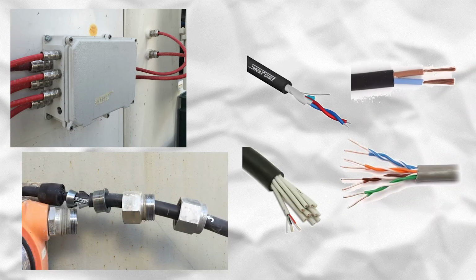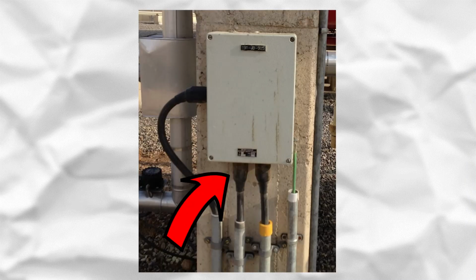In the construction stage, a contractor would follow the drawing designed in the engineering stage and install the measuring instrument on its tap. To design the hookup drawings, an instrument engineer needs to have enough experience and knowledge to implement all the drawings. After all, when it comes to wiring and termination, we face junction boxes, cable glands, and instrument control cables. To design an appropriate JB, bear in mind that the single cables related to measuring instruments should be entered from the left and right side of JB symmetrically, while the multi-cables which integrate all signals and transfer them to the control room must be extracted from the bottom.